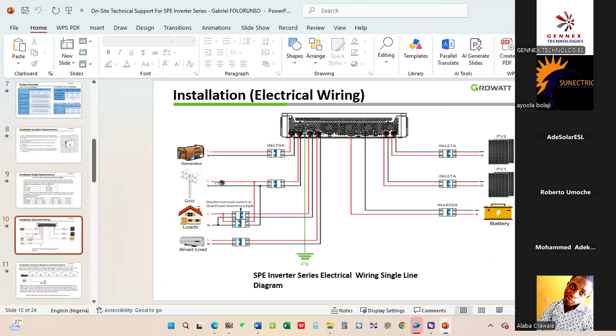If you look closely, for the PV side there are 2 inputs, each with their own individual MCB breaker, alongside the battery breaker. I've seen some installations where, probably because of cost, they just hook up the inverter to the battery directly, with just a switch on the battery or inverter. That's not good for your health - there's a need for us to introduce a breaker.